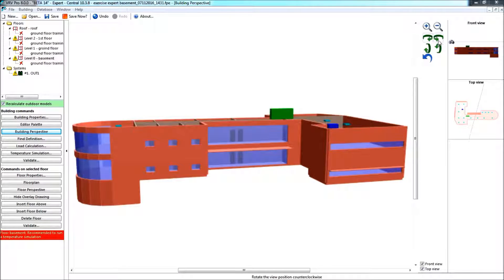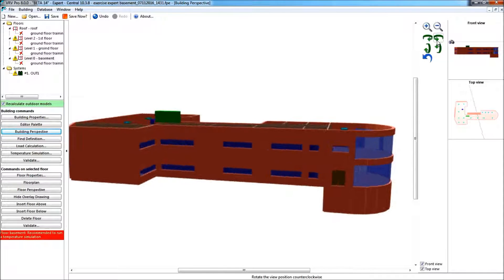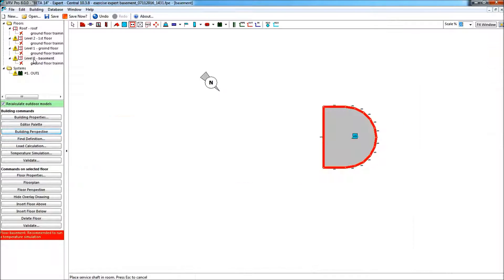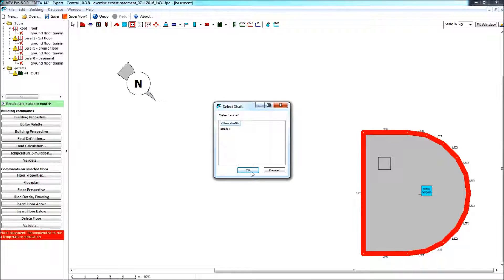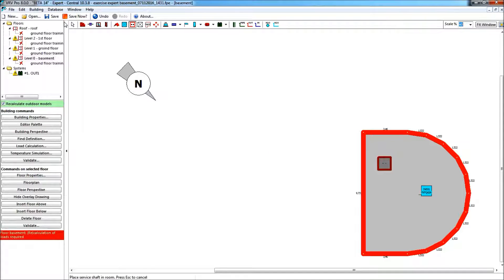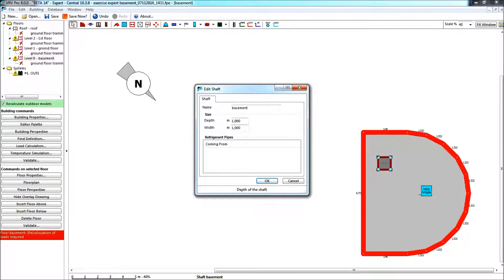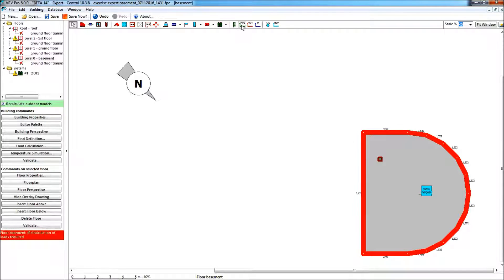I have added a new project, and in that project I have drawn a basement. What I want to show now is how to link shafts, because on the basement floor I did my load calculation and installed an indoor unit. I want to install a shaft on that basement floor. I put the shaft icon there — it is a new shaft that I call 'basement'. I resize it to 0.3 by 0.3, a small shaft for that copper piping. Now I want to link the piping from my indoor unit to my shaft.